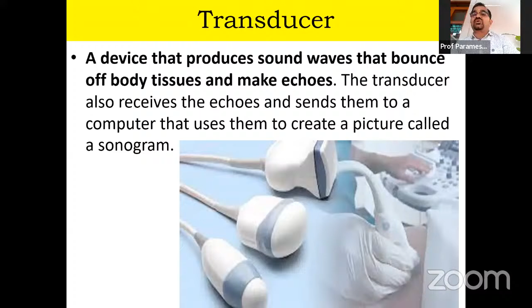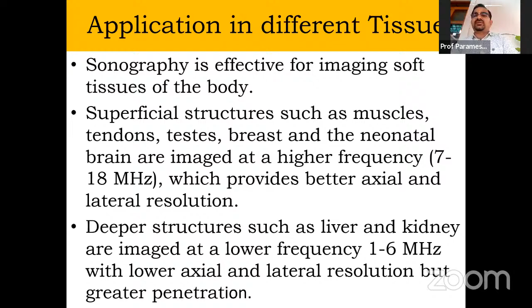This application of ultrasound is very effective for imaging soft tissues of the body. Superficial structures such as muscles, tendons, testes, breast, and neonatal brain are imaged at a higher frequency, 7 to 18 megahertz, which provides a better axial and lateral resolution. Deeper structures such as the liver and kidney are imaged at a lower frequency, that is 1 to 6 megahertz, with a lower axial and lateral resolution but a greater penetration.